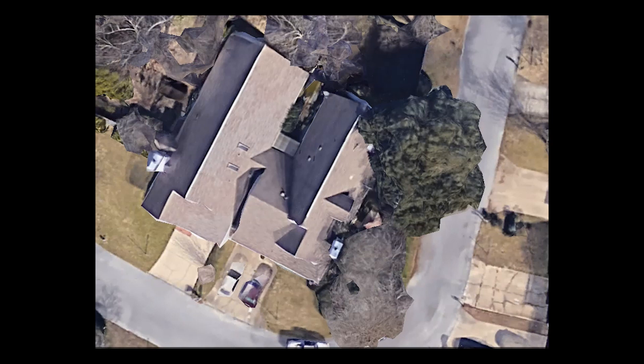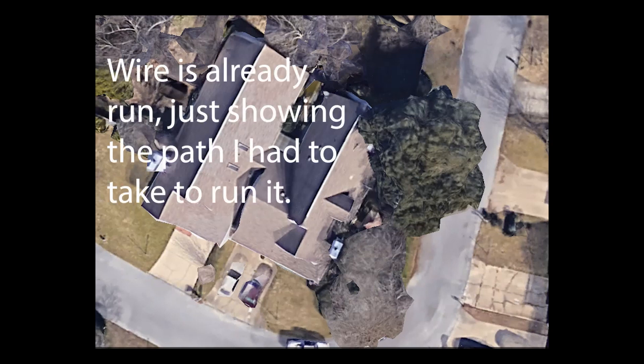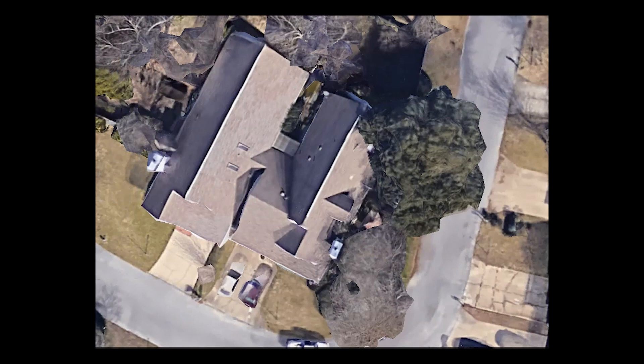Now that I've got my antenna rebuilt, it's time to double-check the ground for the ham shack — I want to make sure it's properly grounded and bonded. This is an aerial shot of my property from Google Earth. My challenge is that my antenna is located at one end of the house whereas the utility grounding is at the other end. I'm going to have to run between 100 and 150 feet or more of 8 AWG bare copper grounding cable around the back of the house, through a privacy fence, behind some bushes, through another set of privacy fences, around the chimney, and terminate right here.